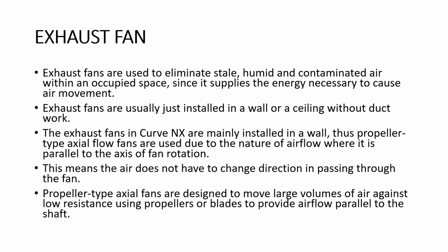Mechanical ventilation system in Curve NX. So the first part is exhaust fan. Exhaust fans are used to eliminate stale, humid, contaminated air within an occupied space, since it supplies the energy necessary to cause air movement. Exhaust fans are usually just installed in a wall or a ceiling without ductwork. The exhaust fans in Curve NX are mainly installed in a wall, thus propeller-type axial flow fans are used due to the nature of airflow, where it is parallel to the axis of fan rotation. This means the air doesn't have to change direction in passing through the fan. Propeller-type axial fans are designed to move large volumes of air against low resistance using propellers or blades to provide airflow parallel to the shaft.